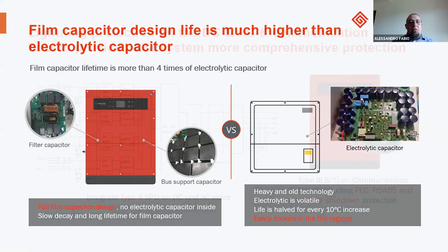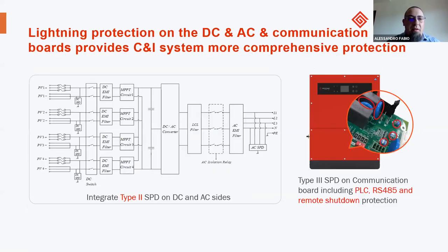As mentioned before, we also have protection inside, so DC and AC protection with SPD. Integrated is a Type 2 on the DC and AC side, and for communication it is Type 3 for the RS-485 communication and PLC communication, also integrated inside. This is a board that you can change, so they are soldered inside, but you can also change the AC and DC SPD protection.